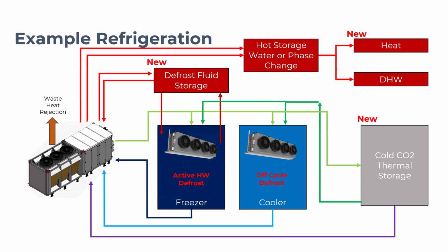On the refrigeration side, you can see a lot going on here, but it's the same exact heat pump, same exact applications. This time we're running a liquid feed out to some cold evaporators in freezers and coolers. We can now embrace simultaneous heating and cooling and do things like hot fluid defrost that's milder, gentler, and a lot more dynamic and responsive. We don't have to pay for electric resistance or reverse cycle hot gas defrost and all the associated energy - you make all your heating while you're cooling. We can also add in CO2 thermal storage, shown on the bottom right, and optimize for peak load shifting, bringing industrial cold into a much more volume-dense form factor. CO2 is about 9 times more energy dense than water, so everything gets smaller, making industrial level cooling storage possible. Add in the fact that you can make hot out of the system, and it's really incredibly robust for an entire facility.